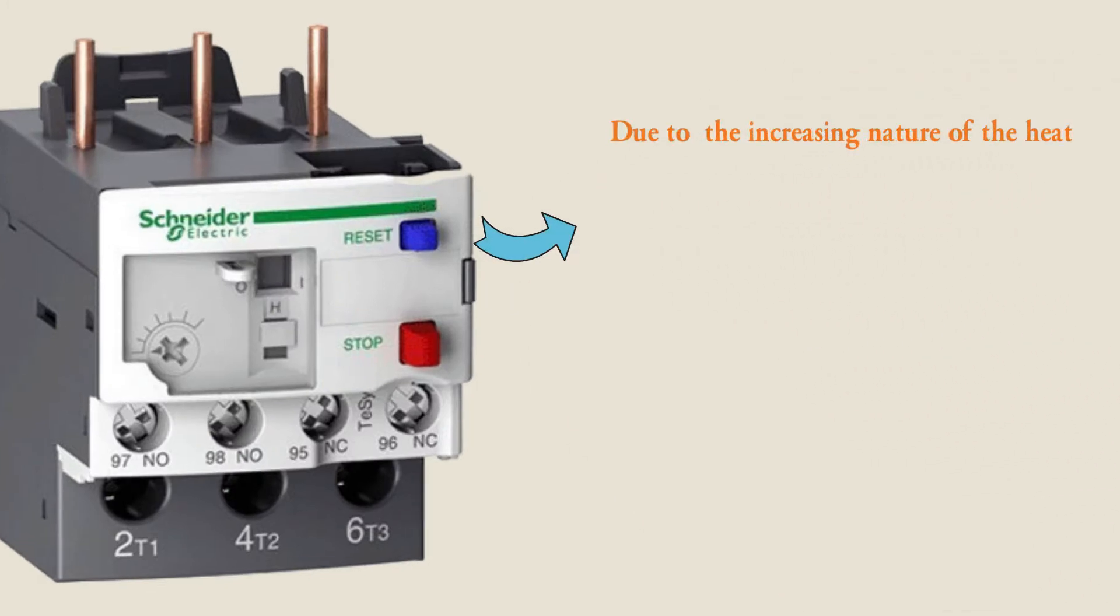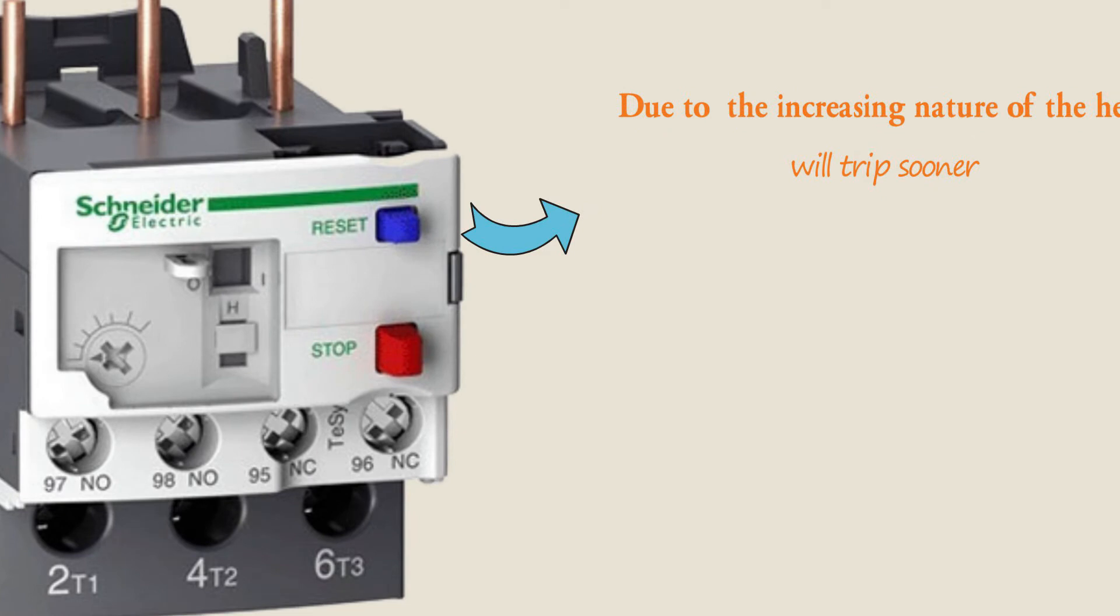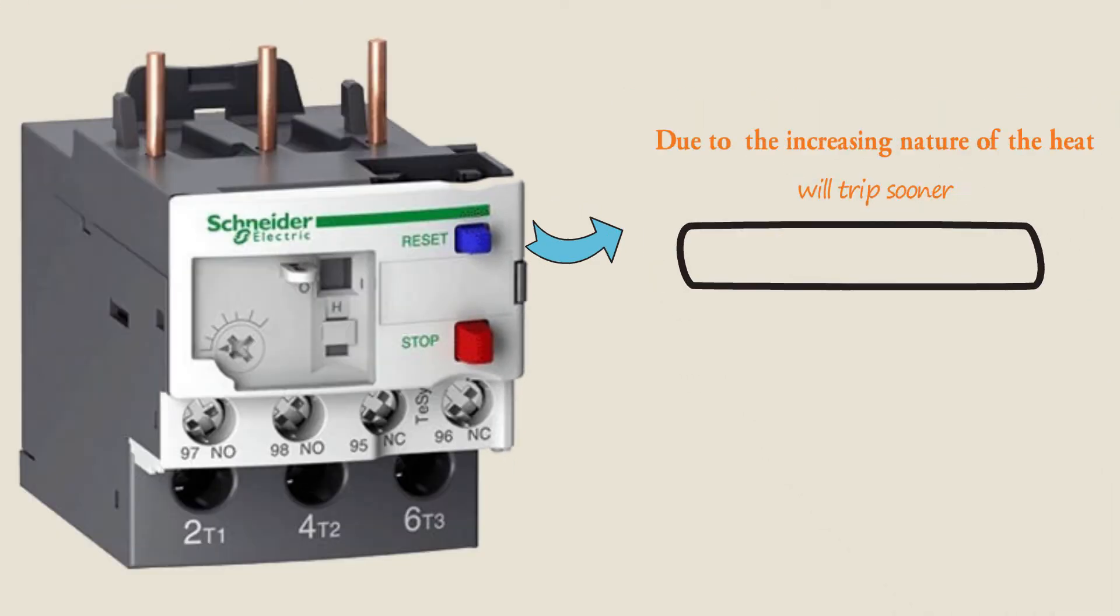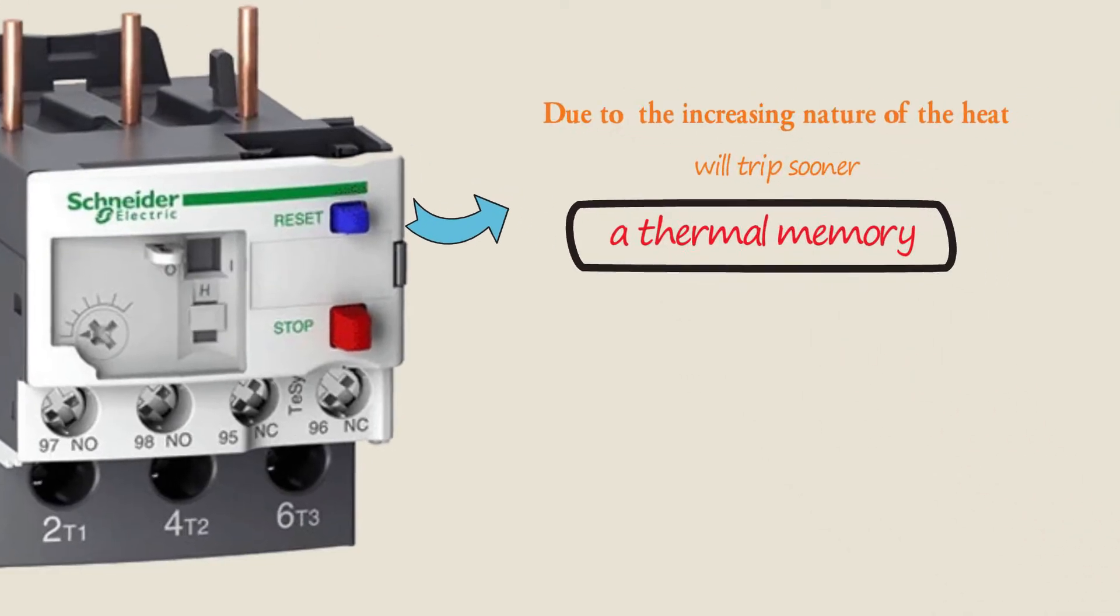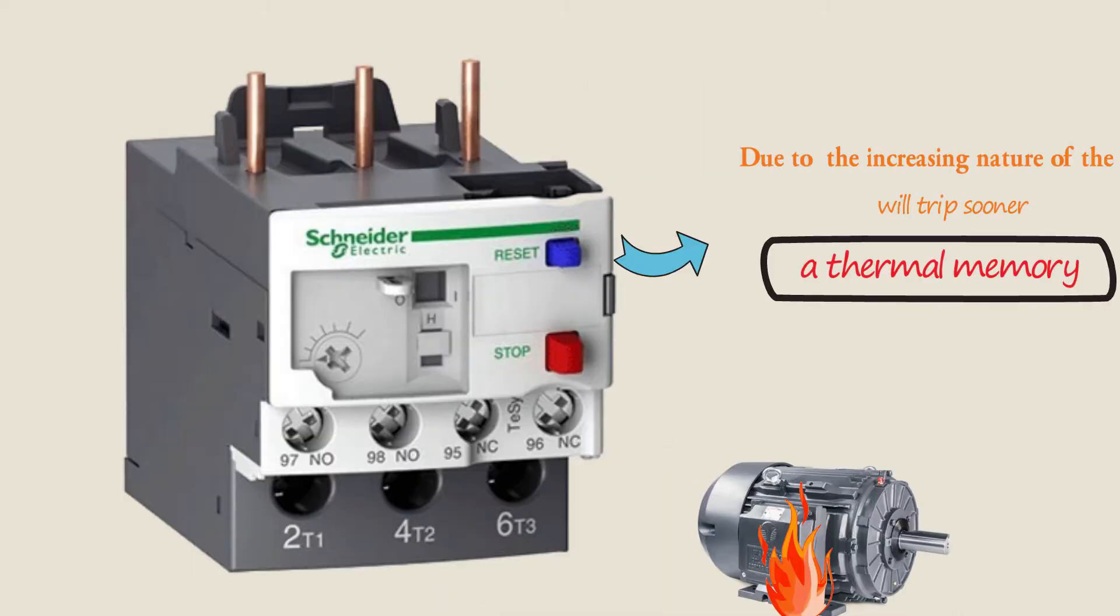The overloads that are previously triggered will trip sooner because of something commonly called thermal memory. Motor damage can happen if the overload relays repeatedly reset without correcting the cause of the overload event.